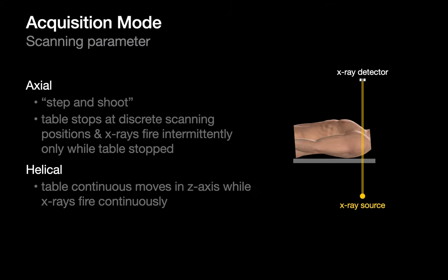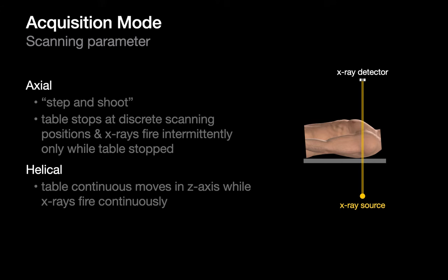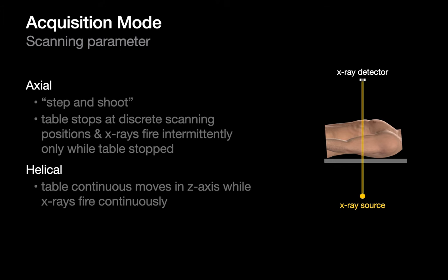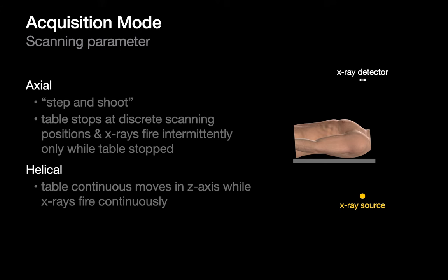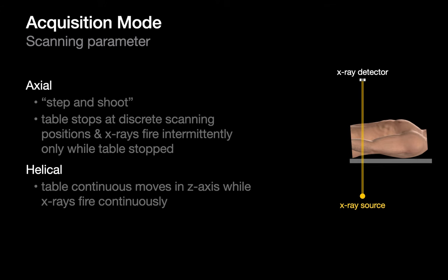The acquisition mode refers to how the CT volume is captured from start to end point. One option is axial (step-and-shoot) acquisition — the earliest method — where the tube turns on, a gantry rotation occurs at one spot, the table moves an increment, and the process repeats until the region is covered. The other option is helical (spiral) acquisition, used for most CT scans today, where the tube remains on as the gantry constantly rotates while the table smoothly moves from start to end point, painting a tight continuous spiral.